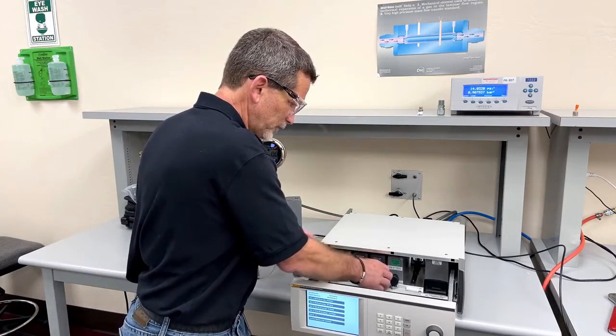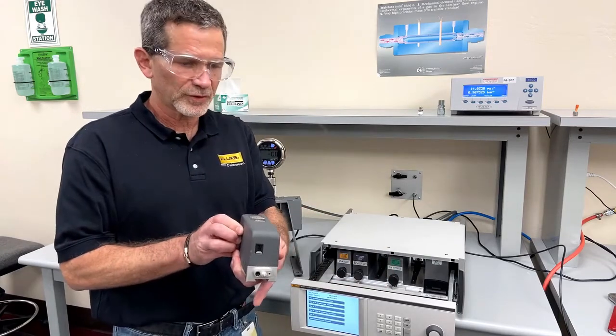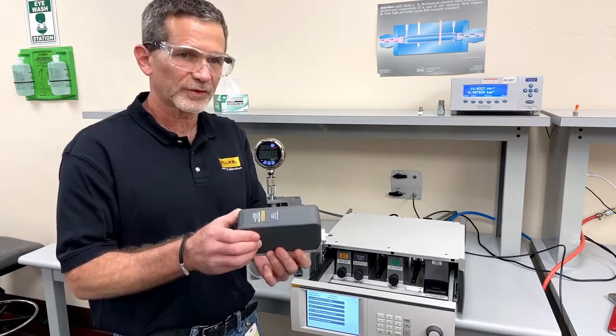When it's time to calibrate the measurement module, take the thumb wheel, spin it, take out the module that you're trying to calibrate. You can see it takes less than two or three seconds.